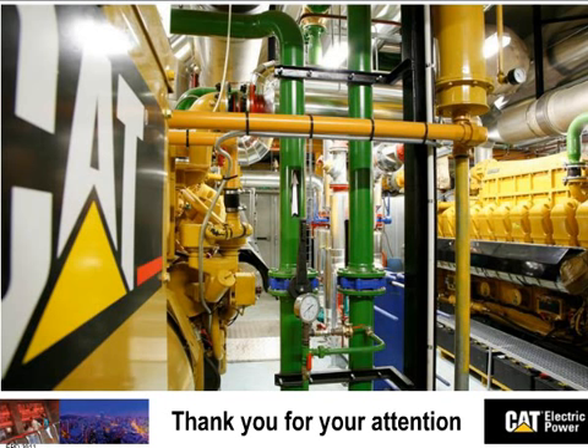So, if you would want to have one steam generator per genset, because you want flexibility and availability, then you would normally go to a small 1 ton per hour type of a steam boiler. Then you will select this kind of manufacturer. I don't want to mention too many names on the line today. If you want to combine the power plant exhaust gases into one large steam generator, then we would use a different steam boiler manufacturer. I hope that answers the question.